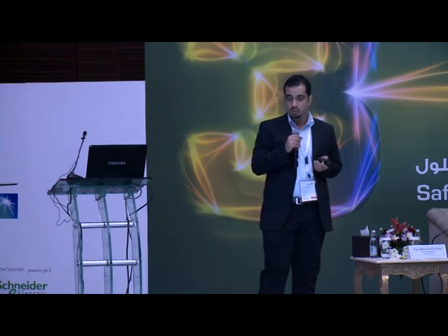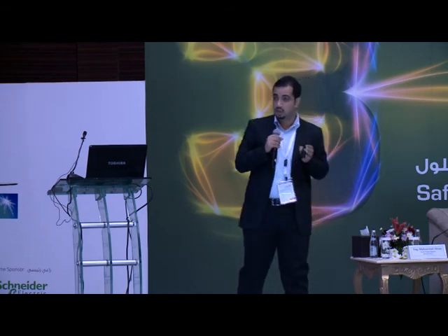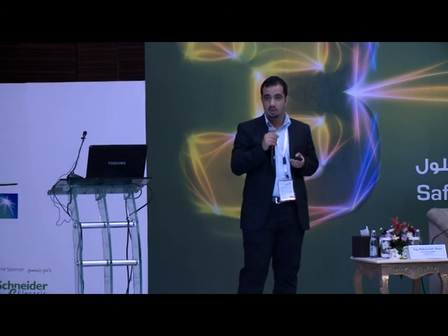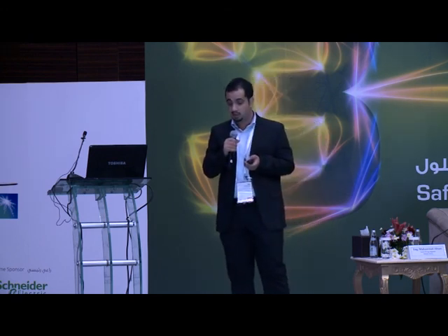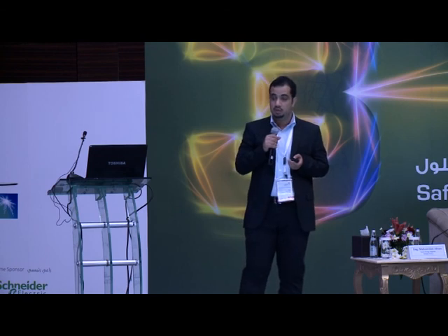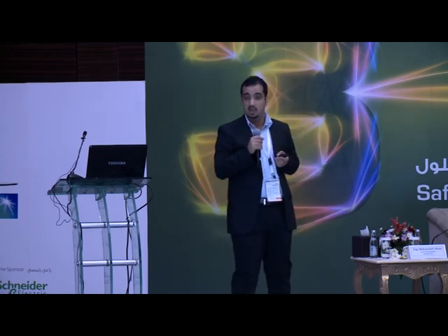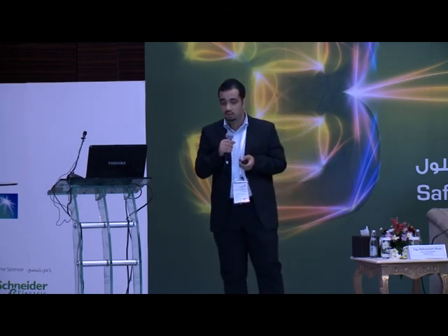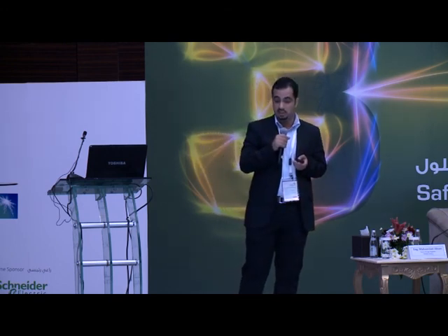Low-voltage equipment is not dangerous. This is not true. As a matter of fact, low-voltage equipment is more dangerous since the exposed parts in the equipment will be more accessible than in high-voltage equipment. More fault clearing time results in a higher arc flash energy. That's true. As you know, time is a factor that will allow the arc to expand. Maximum utility short circuit causes worst case arc flash energy.